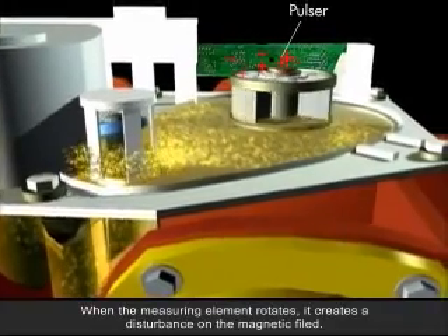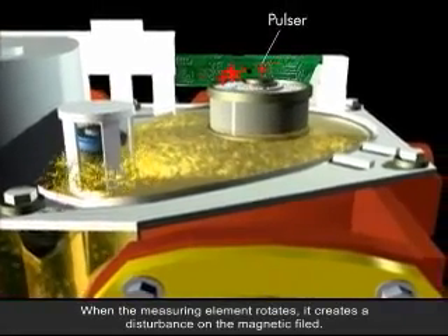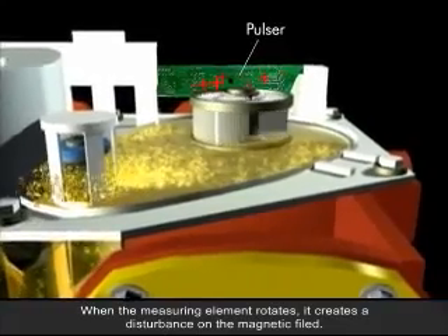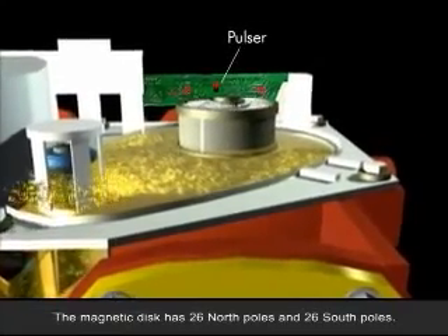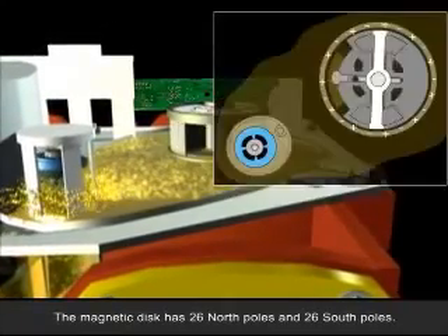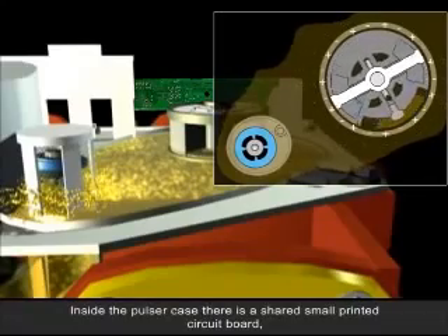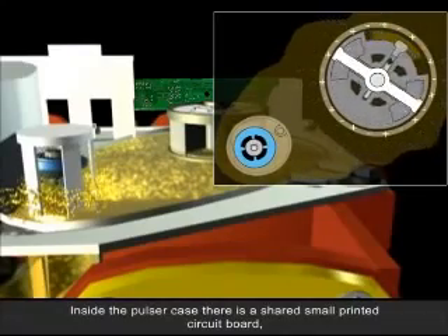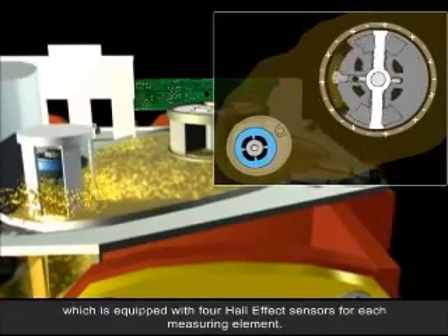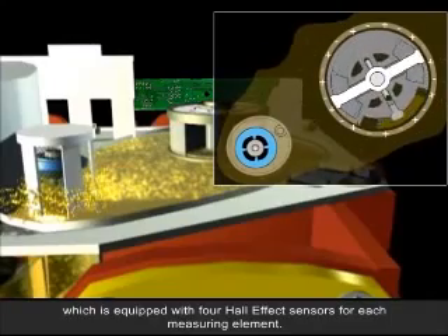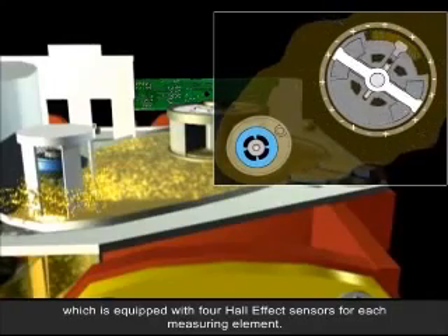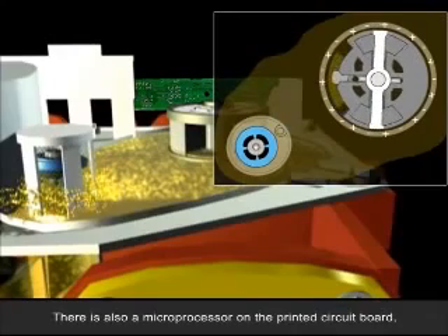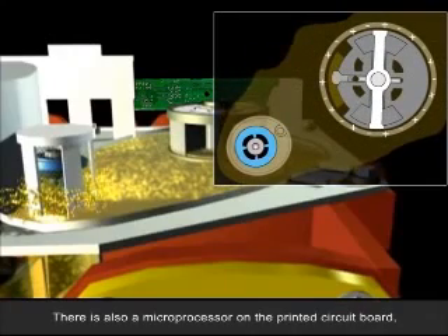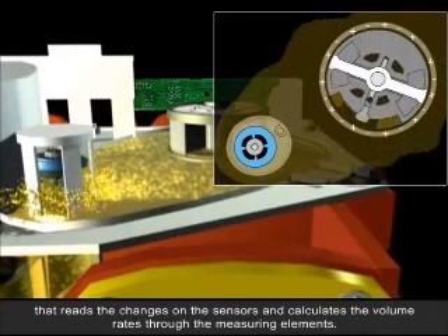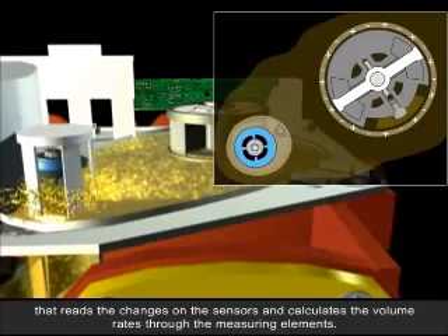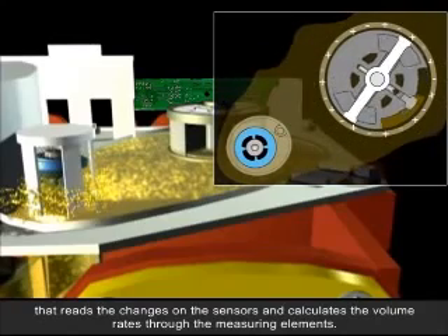When the measuring element rotates, it creates a disturbance on the magnetic field. The magnetic disc has 26 north poles and 26 south poles. Inside the pulser case there is a shared small printed circuit board, which is equipped with 4 Hall effect sensors for each measuring element. There is also a microprocessor on the printed circuit board that reads the changes on the sensors and calculates the volume rates through the measuring elements.